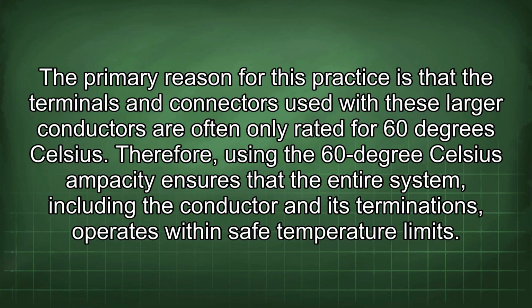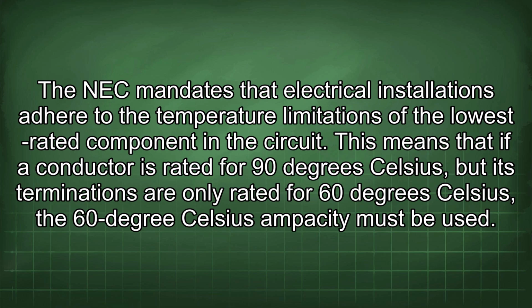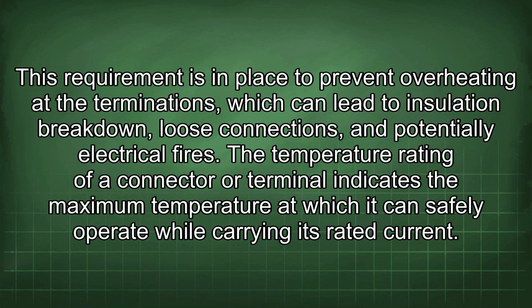Therefore, using the 60 degrees Celsius ampacity ensures that the entire system, including the conductor and its terminations, operates within safe temperature limits. The NEC mandates that electrical installations adhere to the temperature limitations of the lowest rated component in the circuit. This means that if a conductor is rated for 90 degrees Celsius but its terminations are only rated for 60 degrees Celsius, the 60 degrees Celsius ampacity must be used. This requirement is in place to prevent overheating at the terminations, which can lead to insulation breakdown, loose connections, and potentially electrical fires. The temperature rating of a connector or terminal indicates the maximum temperature at which it can safely operate while carrying its rated current.